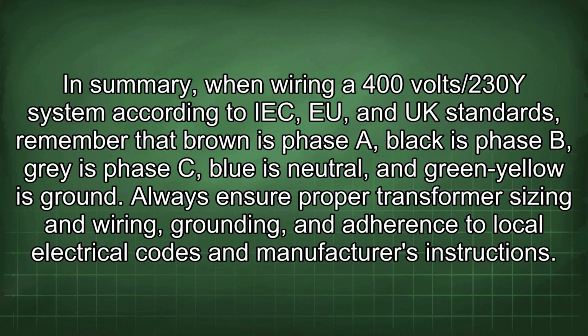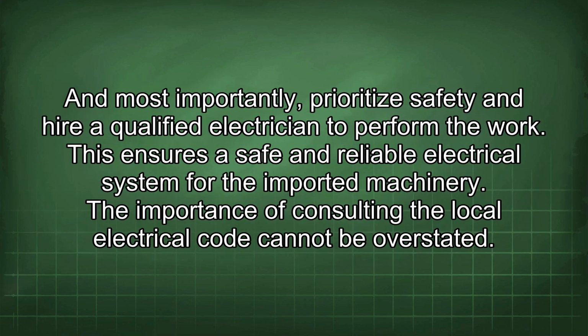In summary, when wiring a 400 volt/230Y system according to IEC, EU, and UK standards, remember that brown is phase A, black is phase B, grey is phase C, blue is neutral, and green-yellow is ground. Always ensure proper transformer sizing and wiring, grounding, and adherence to local electrical codes and manufacturer's instructions. And most importantly, prioritize safety and hire a qualified electrician to perform the work.